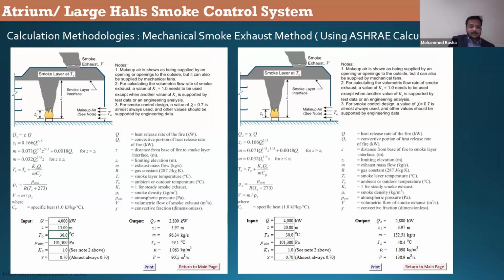And this is the density of the smoke, 1 kilogram per meter cube. And this is the volumetric flow rate, 90.6 meter cube per second. Here you can see M, the exhaust mass flow, which is how much smoke is coming, 96 kilogram per second. When I convert that into volumetric flow rate, which is the fan size, V, it is 90.6 meter cube per second.